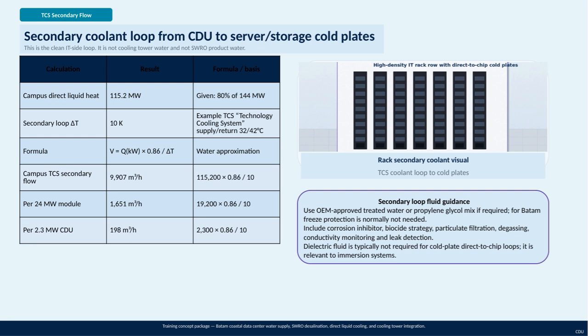The temperature difference in the secondary loop is around 10 Kelvin, with supply and return temperatures at approximately 32 and 42 degrees Celsius, respectively. Using this temperature difference in heat load, we calculate the required cooling water volume flow. For example, the overall campus TCS secondary flow comes out to roughly 9,907 cubic meters per hour. Breaking it down further, a 24 megawatt module needs about 1,651 cubic meters per hour, while a single 2.3 megawatt CDU requires about 198 cubic meters per hour. These calculations ensure the system maintains optimal cooling capacity.